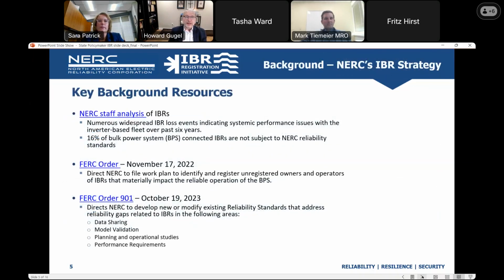This started back in 2020, 2021 timeframe, when we at NERC and also at various regions were beginning to see a significant increase in inverter-based resources, and begin to see these trends on event reports that were occurring. What we had noticed was almost 16% of bulk power system connected IBRs were not subject to our mandatory and enforceable reliability standards, but were showing to be impactful.